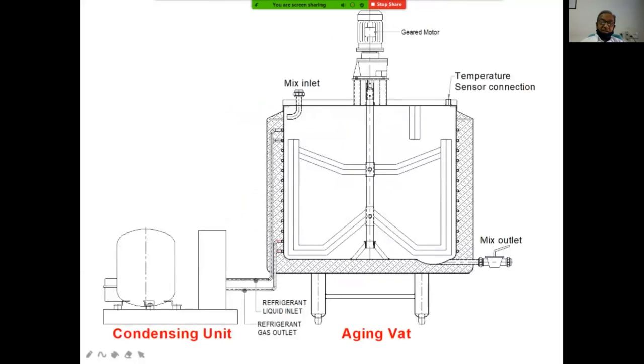In case it is refrigerated, instead of the chill water, the refrigeration system is connected, a condensing unit is connected, and then there is a copper coil. This copper coil is brazed or soldered on the outer wall of the tank, and it supplies the cooling effect to the mix and tries to maintain the temperature at +4 degrees centigrade. What is required? This is the simple structure of the ageing vat.